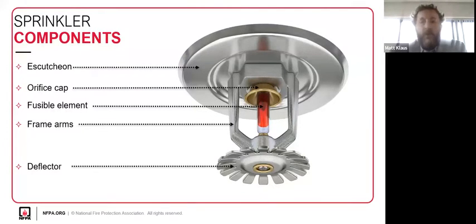The right way: this device has a fusible element. In the olden days it was a piece of metal designed to melt away at a certain temperature. Now we primarily use glass bulbs, though you'll still see fusible links. The idea is when that fluid gets hot, the liquid expands, breaks the bulb, and water comes down through the orifice cap, hits the deflector, and creates a spray pattern.